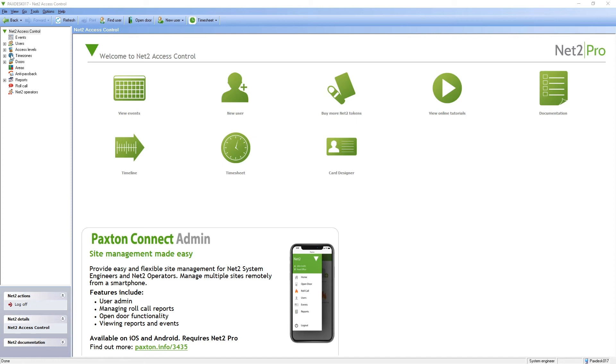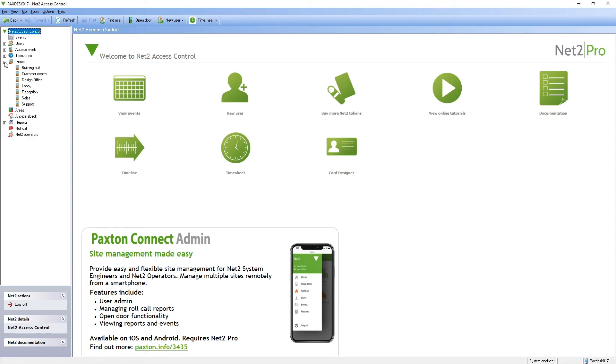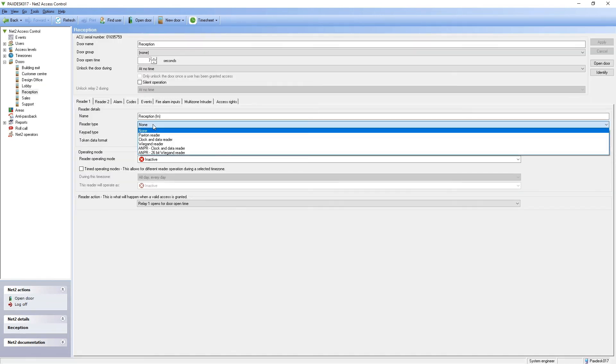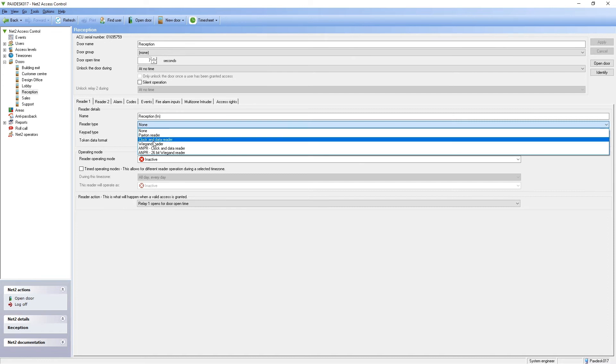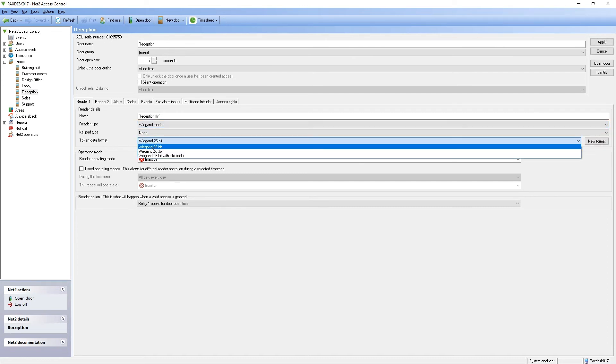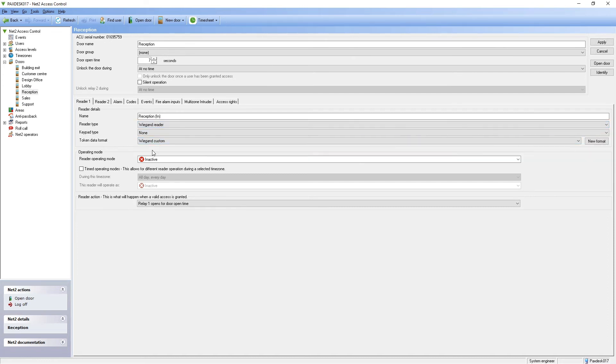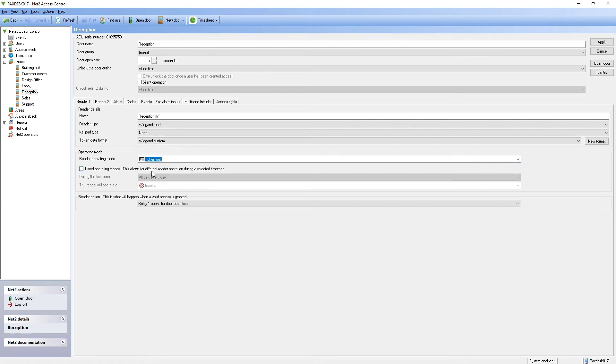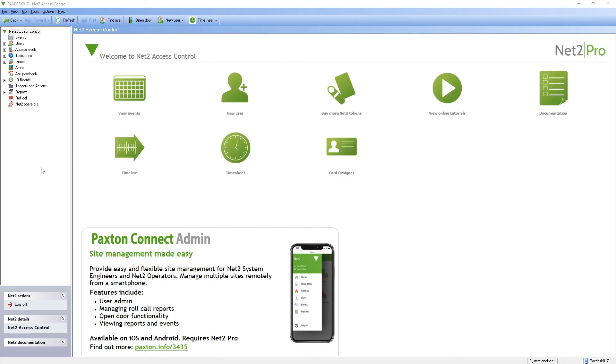The custom format now needs to be applied to the control unit in the NET2 software. Click on doors and select the relevant door. Set the reader type to Wiegand reader. Change the token data format to Wiegand custom. Amend the reader operating mode to token only and apply to save the settings. The thermal scanner is now ready to be used with NET2.